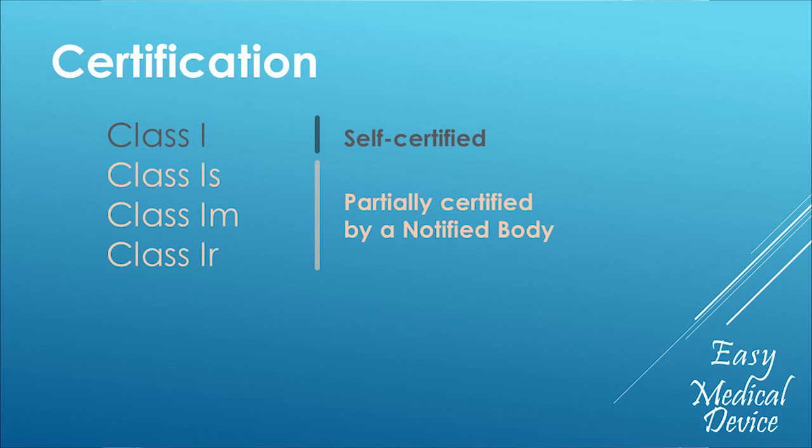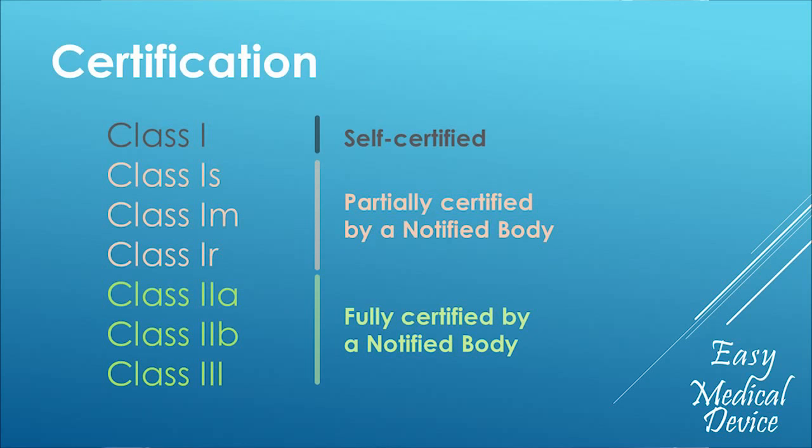For products that are Class 1 but sold sterile, with a measuring function, or reprocessed, it's a bit more difficult — they are partially certified by a notified body. The notified body is not certifying the full product; it's just certifying one of those three functions: sterilization, measuring function, or reprocessing. They will come to your site and verify how you are sterilizing your products and the validations done, the calibration for measuring function, or the cleaning and its validation for reprocessing. For products that are Class 2a, 2b, or 3, those are fully certified by your notified body, and you need to contact the notified body to come and audit your site or your product.